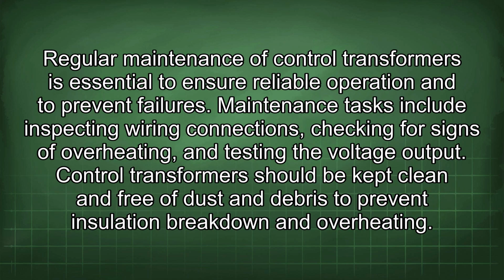Regular maintenance of control transformers is essential to ensure reliable operation and to prevent failures. Maintenance tasks include inspecting wiring connections, checking for signs of overheating, and testing the voltage output. Control transformers should be kept clean and free of dust and debris to prevent insulation breakdown and overheating.